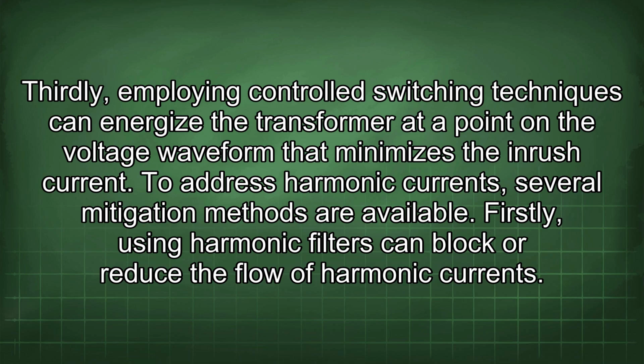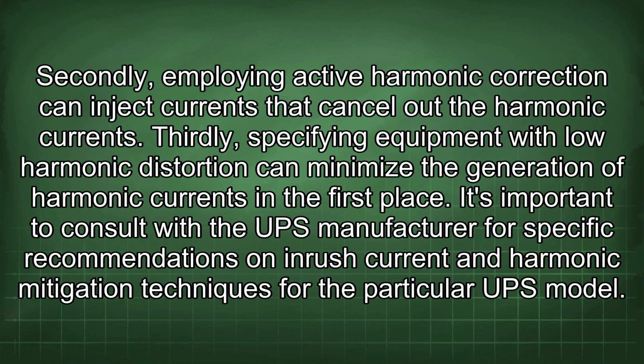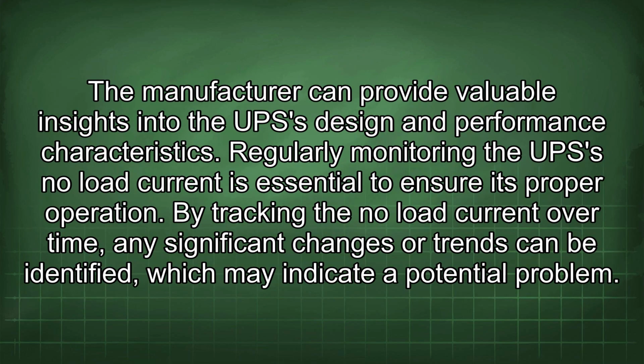Firstly, using harmonic filters can block or reduce the flow of harmonic currents. Secondly, employing active harmonic correction can inject currents that cancel out the harmonic current. Thirdly, specifying equipment with low harmonic distortion can minimize the generation of harmonic currents in the first place. It's important to consult with the UPS manufacturer for specific recommendations on inrush current and harmonic mitigation techniques for the particular UPS model. The manufacturer can provide valuable insights into the UPS design and performance characteristics.